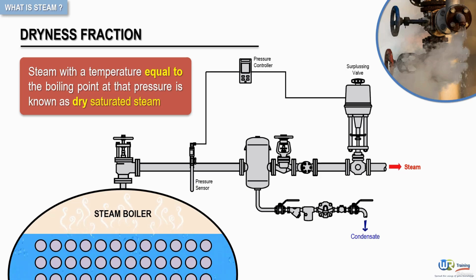In practice, because of turbulence and splashing, as bubbles of steam break through the water surface, the steam space contains a mixture of water droplets and steam. Steam produced in any type of boiler where the heat is supplied only to the water and where the steam remains in contact with the water surface may typically contain around 5% water by mass.